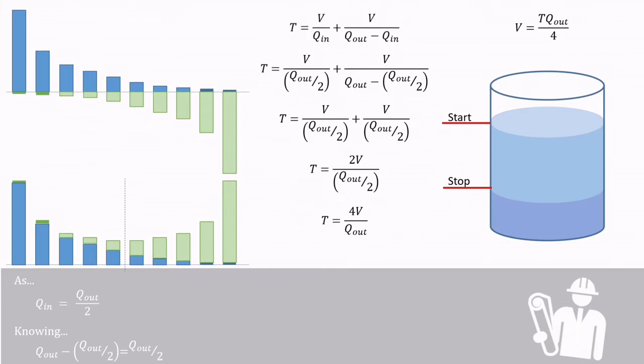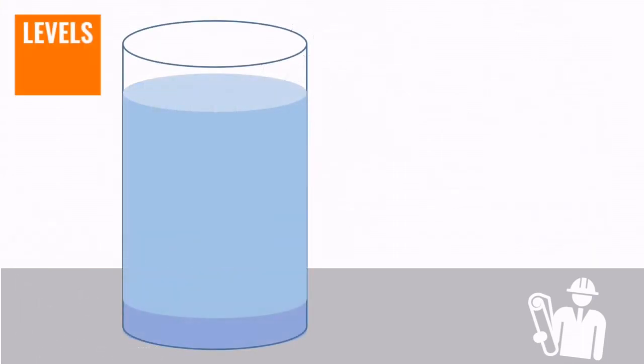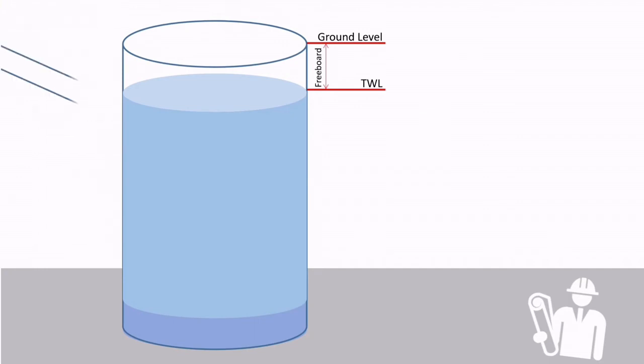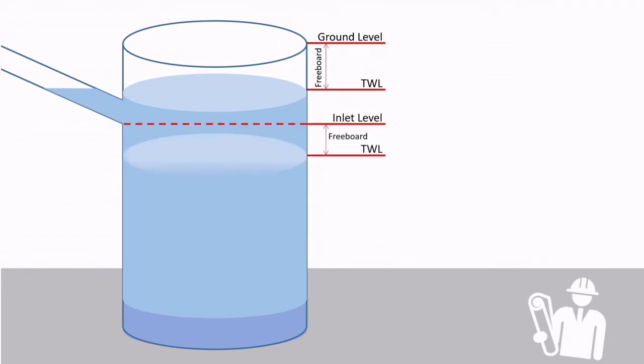Top water level based on freeboard, which tends to be a certain level between the ground level and the maximum water level. However, in some cases like those moving dirty water, this will result in surcharging of incoming pipes and may not be acceptable, in which case the freeboard should be below the incoming pipe.